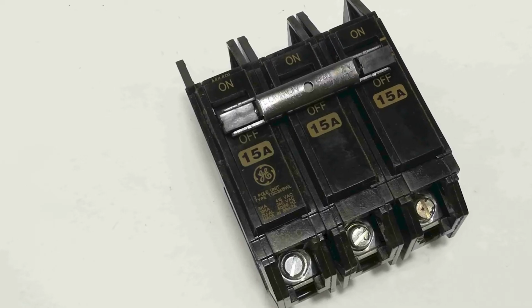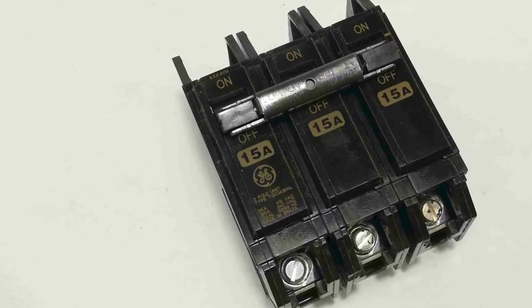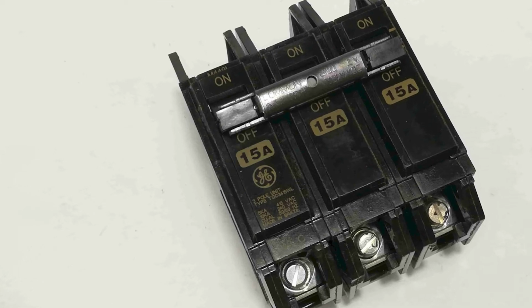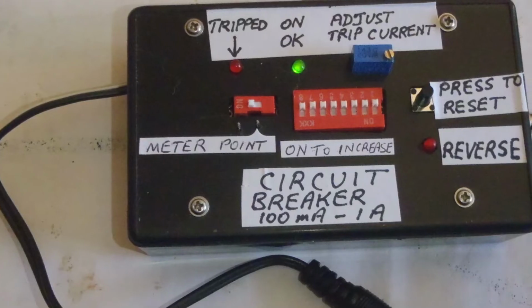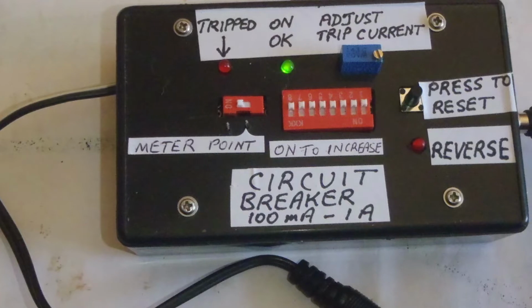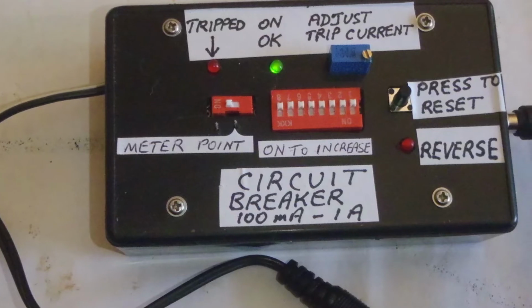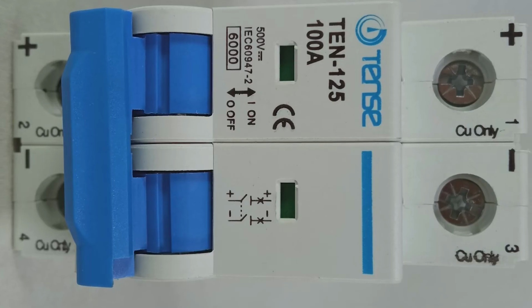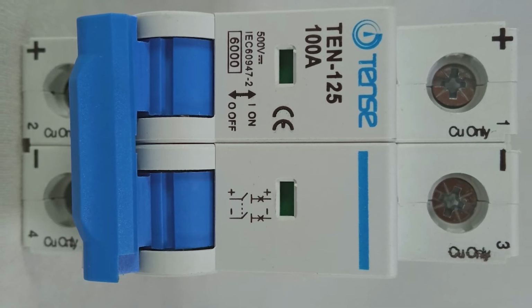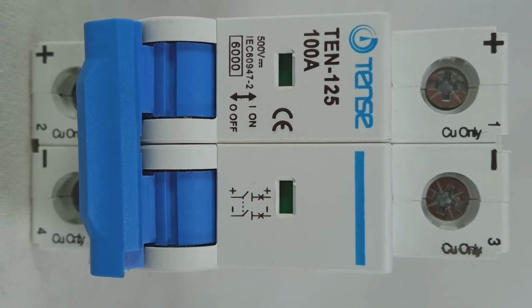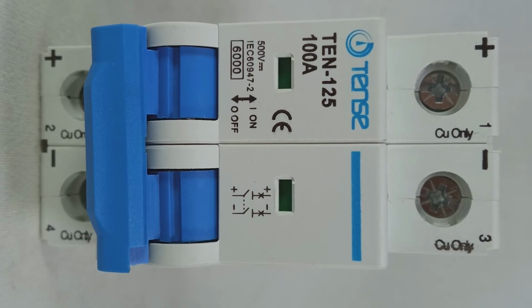More advanced breakers, although even more costly, can be a lot more advantageous. A type of breaker has integrated motors that allow remote opening or closing of the breaker, which you cannot do with fuses, as you need to physically replace a blown fuse. Remote triggering has its advantages, especially when monitoring multiple breakers located far apart from each other.